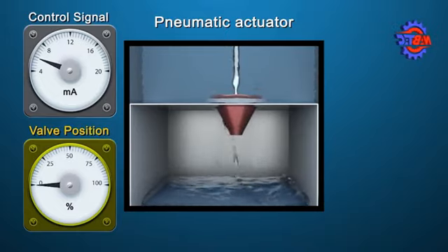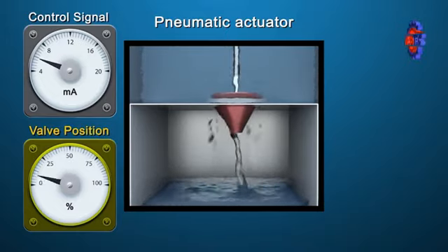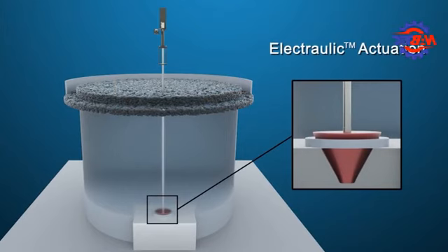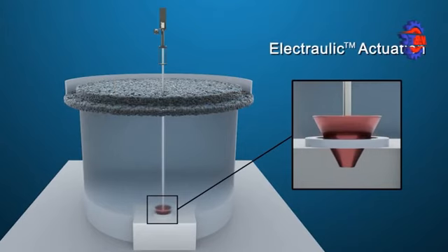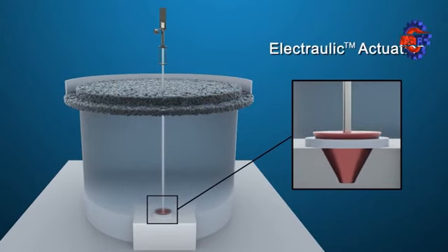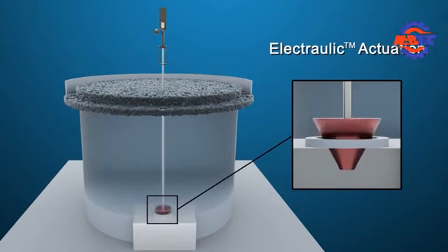If the suction pulls the valve closed, the flow of pulp slurry exiting the cell is disrupted, negatively impacting the neighboring cells. This also creates unnecessary wear on the valve dart and seat. High flow conditions in neighboring cells can require rapid dart valve opening. Immediate response to signal changes ensures the actuator reaches the new target set point quickly and without overshoot.